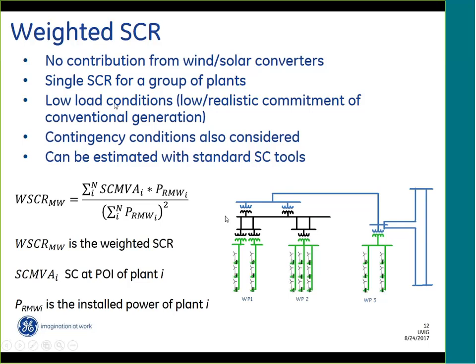And then you would typically calculate this for the weakest conditions because that's what you're concerned about. You're not concerned about the highest short circuit conditions. So you would tend to calculate this for low load conditions and probably contingency conditions. And this tool can be calculated using a standard short circuit tool and some post-processing.